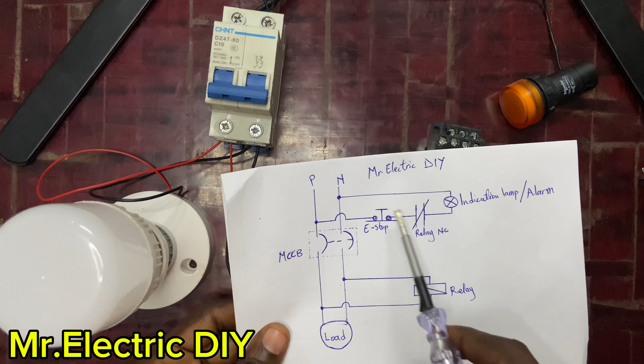So I'm going ahead and connect the emergency stop. We are using the normally closed contact, the normally closed 1 and 2. I'll just connect the live from here to number 1. That's the normally closed, and number 2 to the relay. Now, the only thing you have to take note is that when you are connecting the phase, that is this side, to the emergency stop, you have to make sure that there is no power at this section. There is no power here.